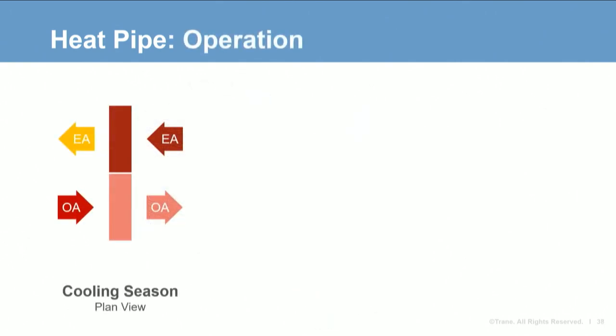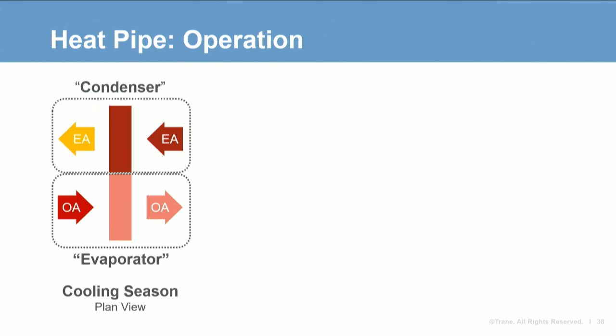Here's an overhead view of a heat pipe illustrating an outdoor air preconditioning arrangement during the cooling season. The outdoor air is warmer than the exhaust air, so the evaporator is in the outdoor airstream and the condenser is in the exhaust airstream. Refrigerant is evaporated by the warmer outdoor air, and the refrigerant vapor pressure increases. The vapor migrates to condense and release heat to the exhaust airstream where the vapor pressure is lower. Liquid refrigerant wicks back to the evaporator section and the cycle is repeated.